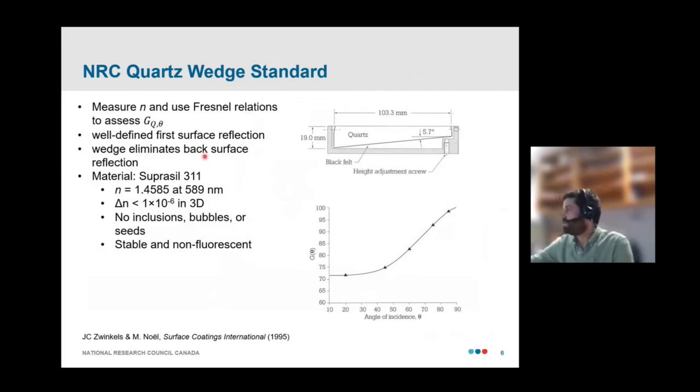So, our quartz wedge standard. I'm just going to really briefly describe these. We've already heard about how this is done. But the basic idea is you have a nice optical material whose refractive index you know, and you can use the Fresnel relations to compute the specular gloss at different angles. We use a wedge geometry to remove this first surface reflection. And as an optical material, we're using a Suprasil 311 glass. And this has a number of nice properties as a reference material. The variations in the refractive index are thought to be at the PPM level. It has very few inclusions or other defects in the bulk of the glass that might lead to some unwanted scattering. And our experience has also been that it's highly stable and non-fluorescent, making it a nice material to use for this purpose.